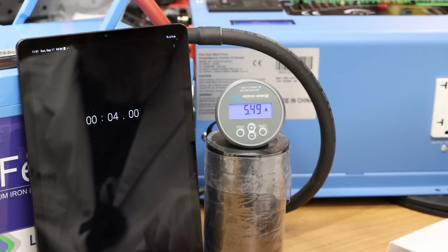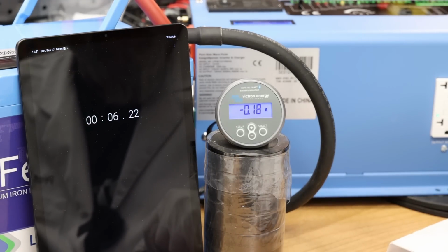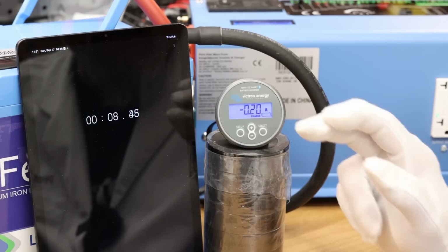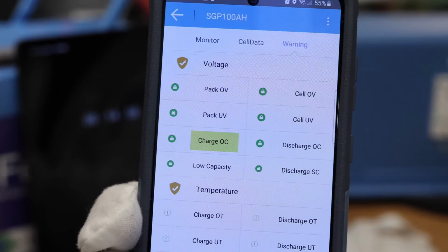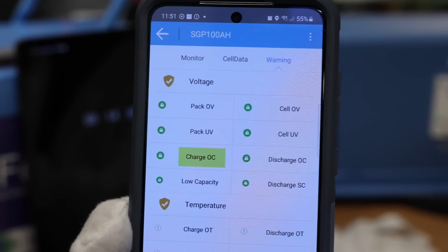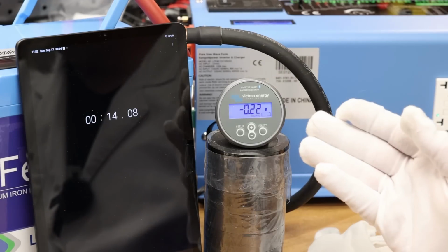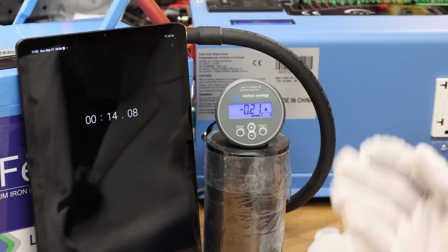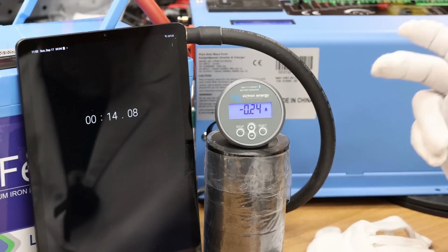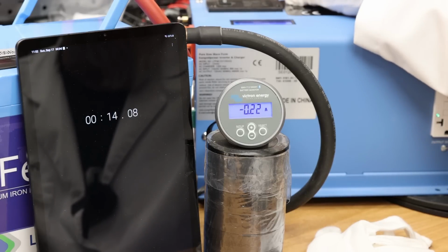We're at the max charge rate, and that didn't take long at all, just seconds, and it shut it down. This time it says charge overcurrent protection is lit up. Because I tried to charge it over 100 amps, it shut down the charging completely in just a matter of seconds. So I'm going to have to dial this thing back down when it resets.